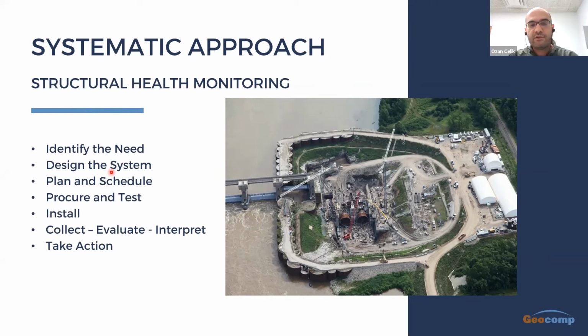Then once you decided what kind of equipment you are going to use, the next step will be planning and scheduling. The project site or the nature of the project might have some tight requirements, tight time limits. So it's very important to plan and schedule with the stakeholders so that nothing is going to be delayed. Then the next step will be procuring and testing your equipment. Although all the manufacturers provide their products with certain calibration and quality assurance documentation, it's always very important to test them in-house before putting in the field as well, just to make sure everything is right and according to what the paper is saying.